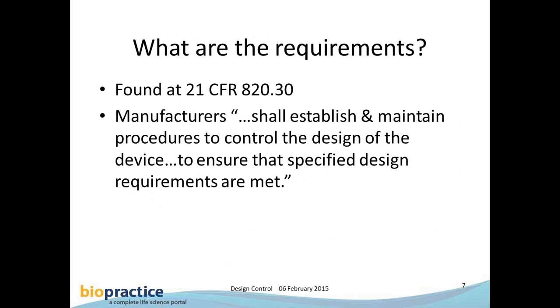Every single clause under the design control section of the regulations says that the manufacturer shall establish and maintain procedures to control the design of the device or to control the particular requirement to ensure that specified design requirements are met.